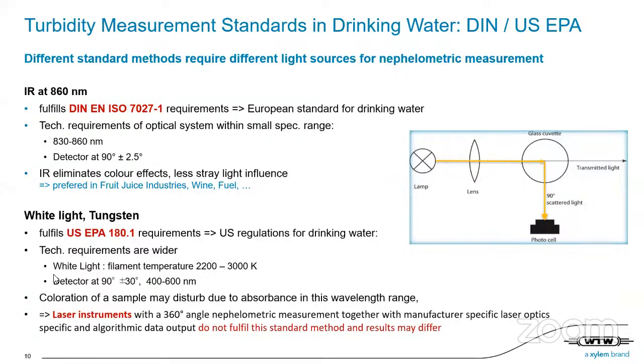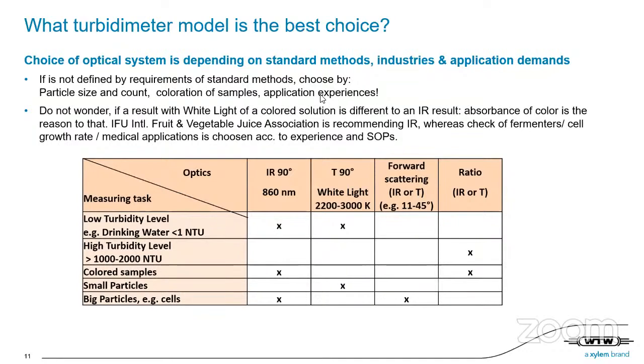And I want to point out that there are laser instruments out there as well, which offer a 360° angle measurement and nephelometric, but usually today, at least as far as I know, they do not fulfill standard methods of the tungsten white light. And therefore, if you compare results between different optics, again, the result might differ. We come to the conclusion later on that it's not important, because if you measure water with different optics which are assigned, no matter if IR or tungsten, you will get the same measurement results if you have a standard method and a standard optic for the instrument.